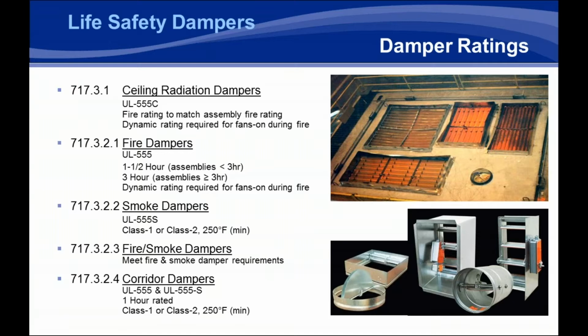As you can see in the top right portion of this presentation, there's the slide, there's a simulated horizontal fire test, and basically that's a fire rated floor that has traditional style fire dampers installed into it. It's a little different than a ceiling radiation or a ceiling assembly test, which would be UL 555 versus UL 263, where it tests the entire rated floor ceiling assembly. So not just the floor, but the ceiling below it as well.